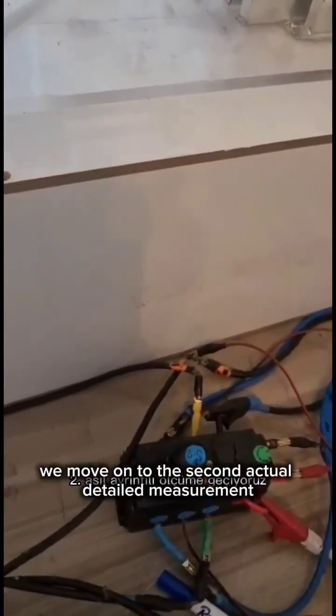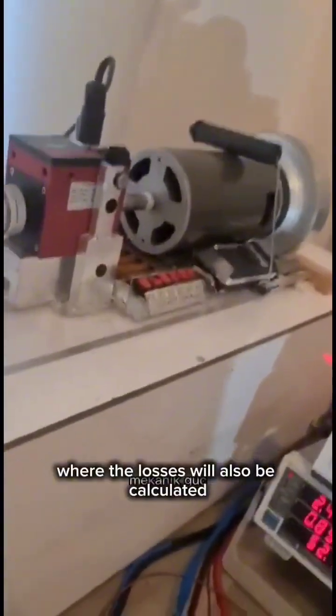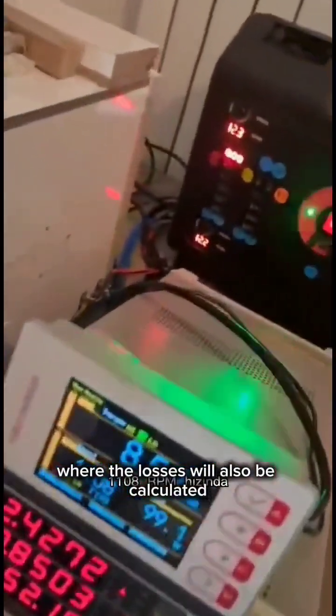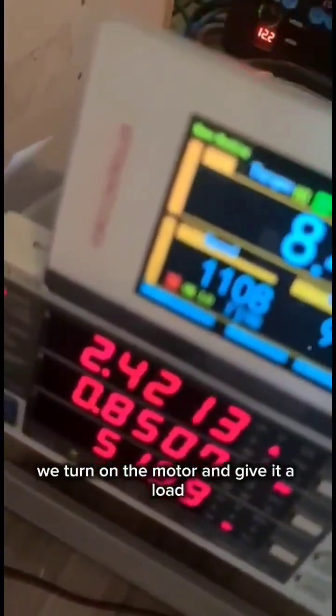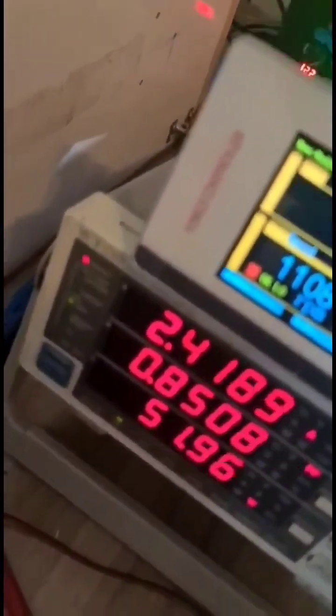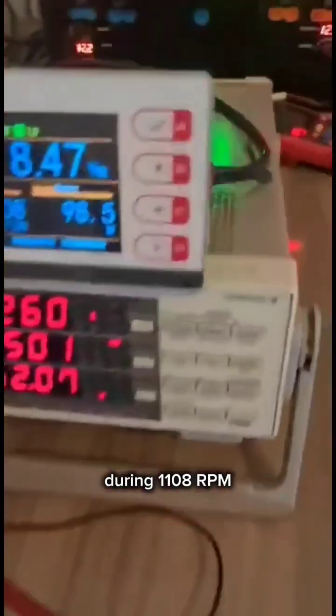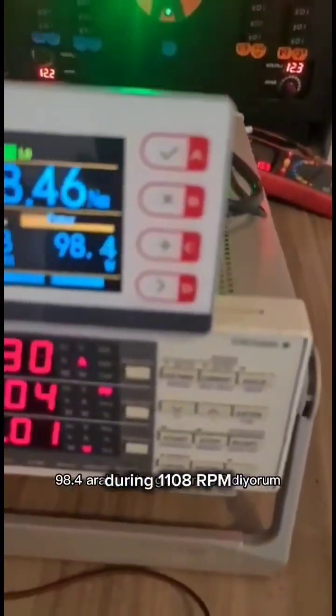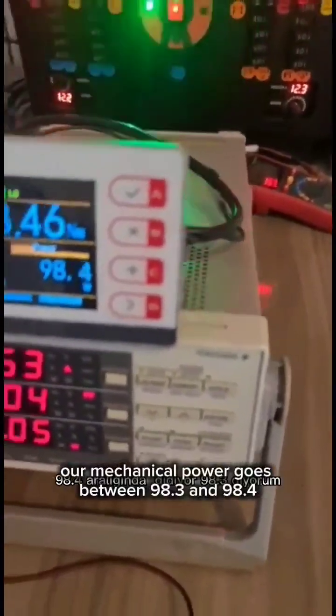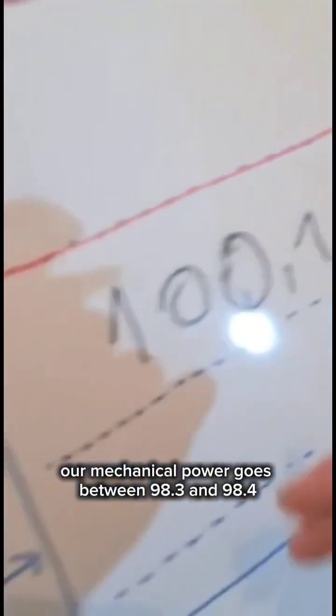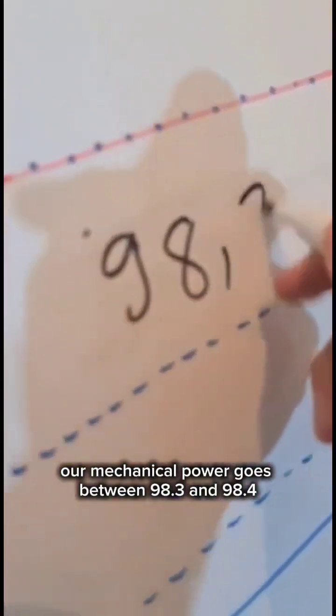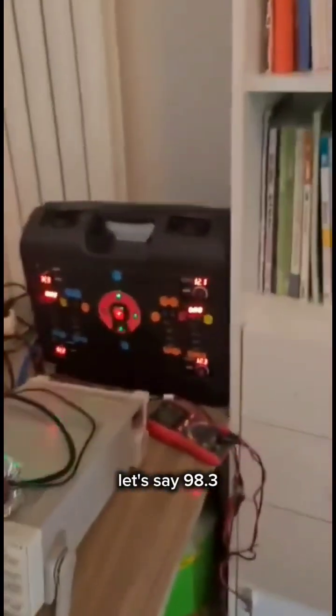Now we move on to the second, more detailed measurement, where the losses will also be calculated. We turned on the motor and gave it a load. At 1108 RPM, our mechanical power goes between 98.3 and 98.4. Let's say 98.3.